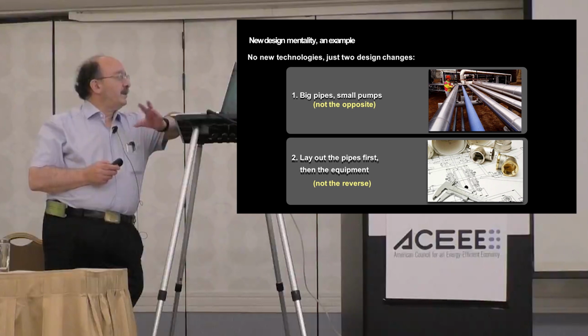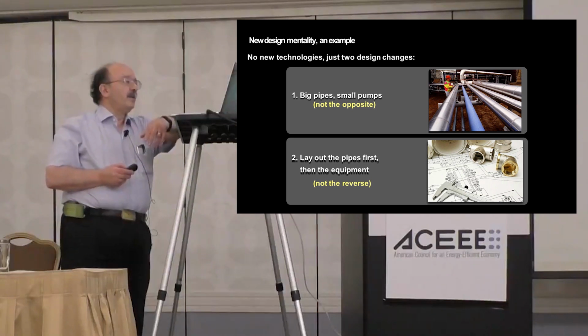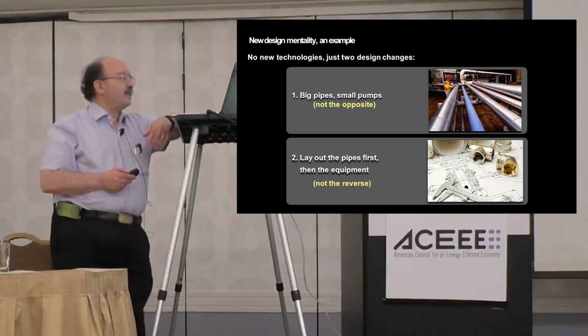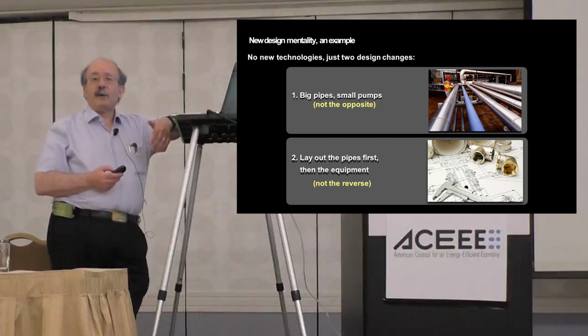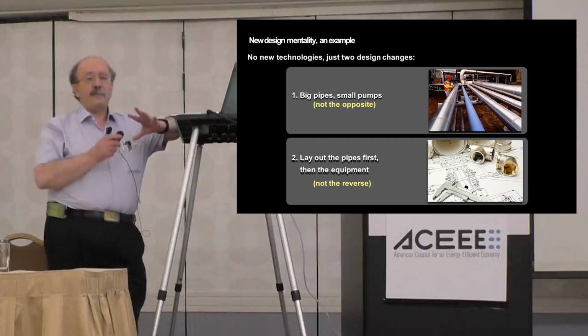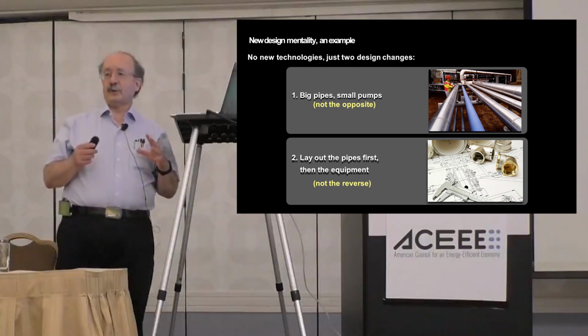Let me dig a little deeper into these two changes in the design process. First, on specifying big pipes and small pumps. Friction in a pipe falls as roughly the 5th power of its diameter. So how fat should the pipe be to optimize the friction?